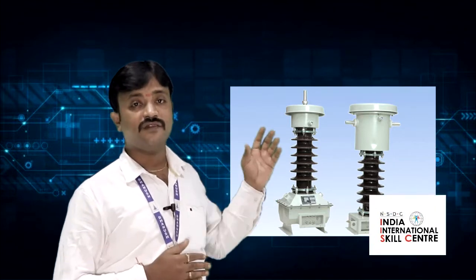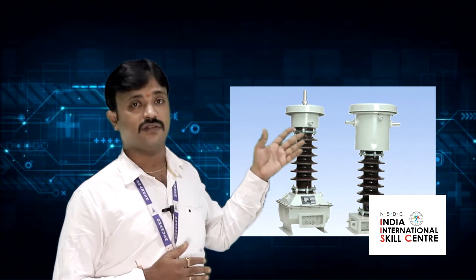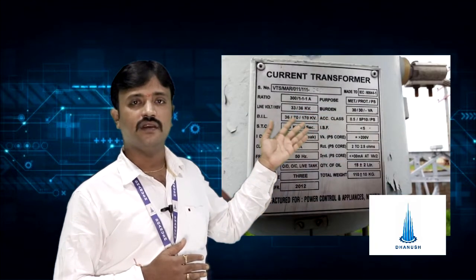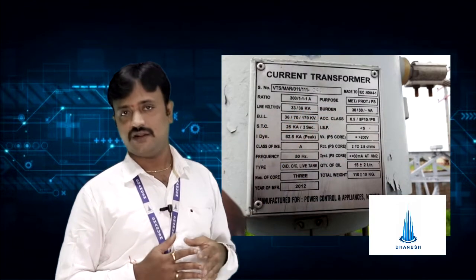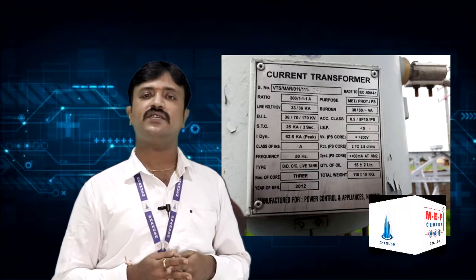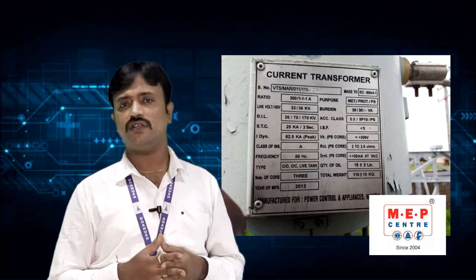So when you're defining the transformer size, we are also going to calculate the CT and PT, current transformer and potential transformer. See, we all know what a CT is, which helps in measuring current, and a PT helps in measuring voltage. So whenever you're defining the CT, we require technical parameters. So as you can see the nameplate rating of the CT, we are going to define the CT and PT calculations.